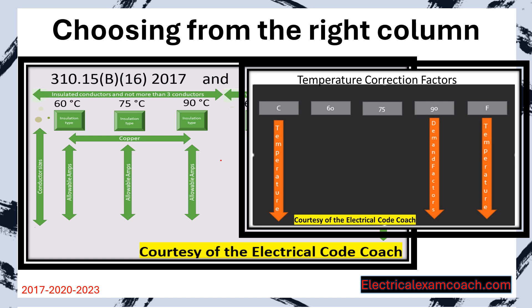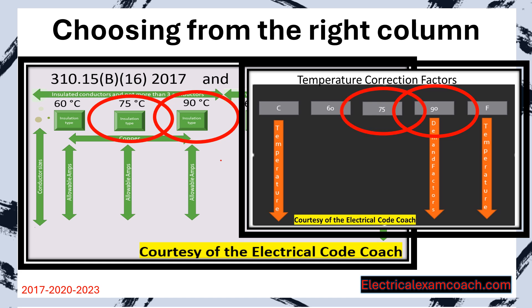Let's talk about choosing from the right column. Just like with bundling adjustments, 99.9% of the time we're going to choose from the 90 degrees C column for our starting ampacity, and we must also choose from the 90 degrees C column in our temperature corrections factor table. In the rare event it's not listed there, we'd choose from the 75 degrees C column — but that would be under very rare circumstances in the testing center.